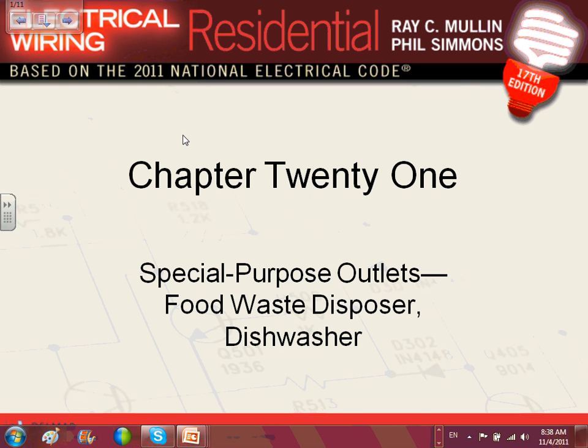The rule for appliances is in Chapter 4, Article 422. It tells you if it's 13 amps or less, use a 20-amp circuit dedicated for it. If it's more than 13 amps, we take the full load current and multiply it by 1.25. Most of these two pieces of equipment — the food disposal and the dishwasher — almost always in residential, the amps are less than 13.